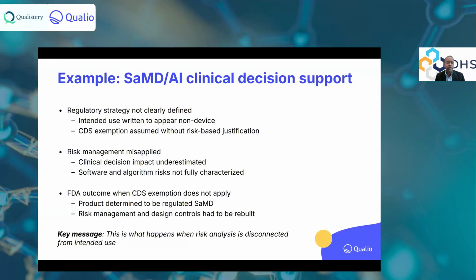I've also seen some use cases where you do some training and that becomes your AI ML tool. And then it has to go through validation, aligned with your intended use and claims you're making. So yes, it's possible to do it both ways.